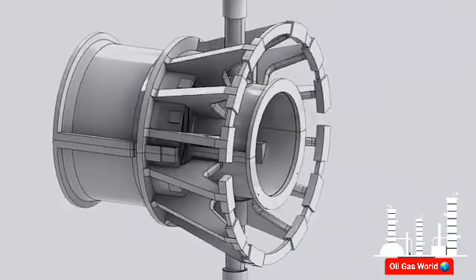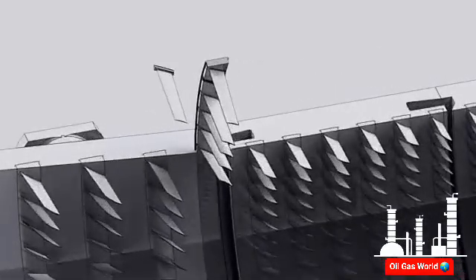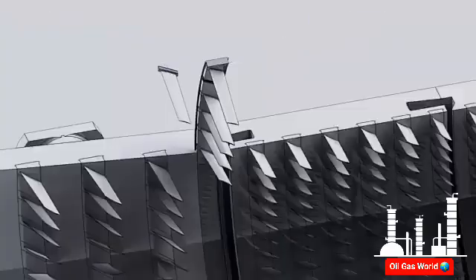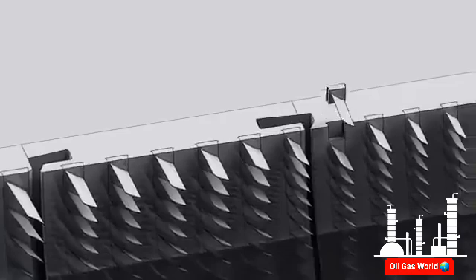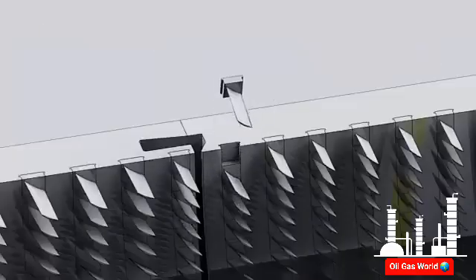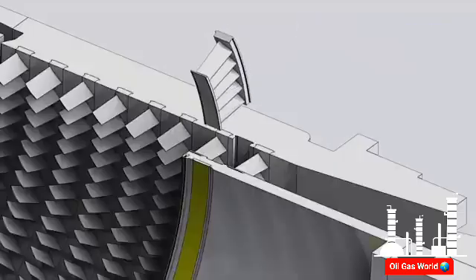The discharge casing also supports the turbine first stage nozzles. The first stage nozzle support ring is mounted on the aft end of the inner cylinder. The stationary vanes of the compressor are airfoil shaped. The blades of the first eight stages are mounted by dovetail arrangement to ring segments, which are inserted into circumferential grooves on the casing. The blades of the last nine stages have a square base dovetail and are inserted directly into the circumferential grooves on the casing. Two rows of exit guide vanes at the end of the compressor help reduce the rotation of the airflow and increase the pressure.